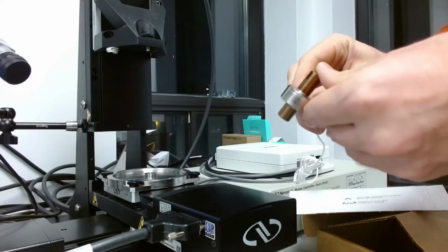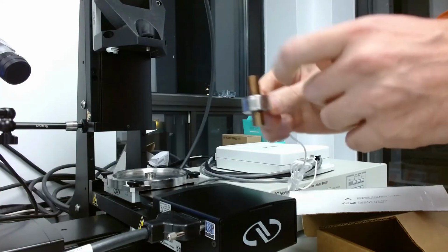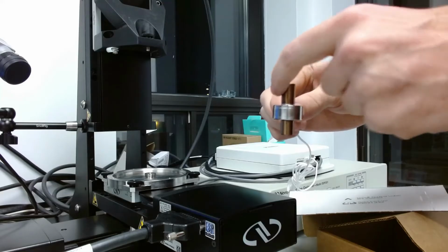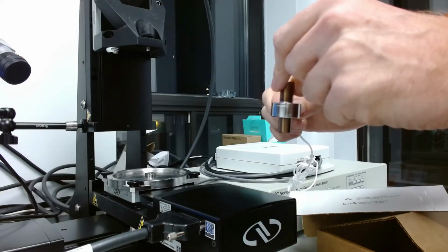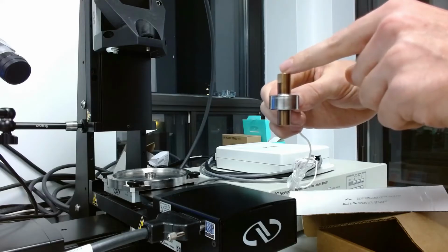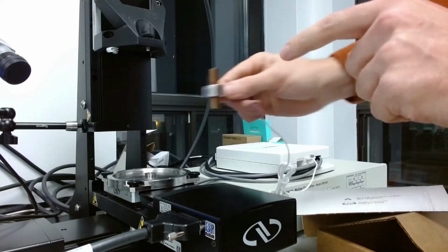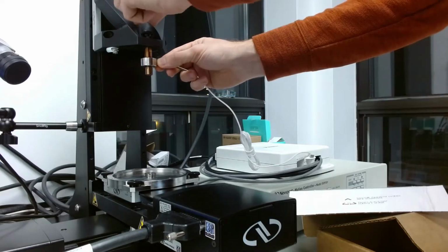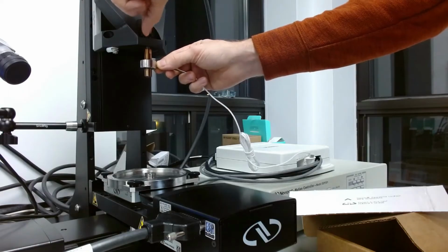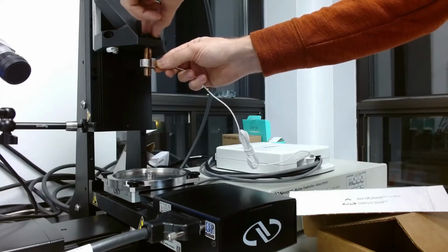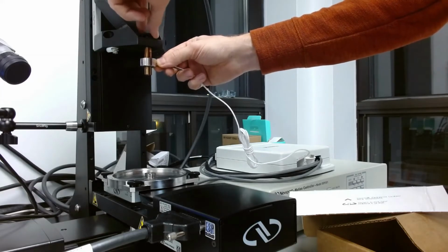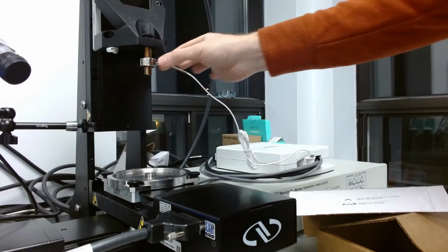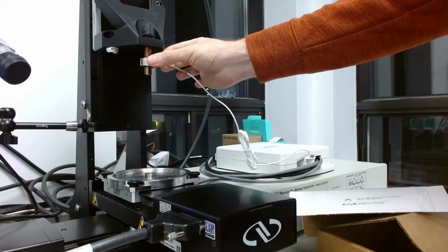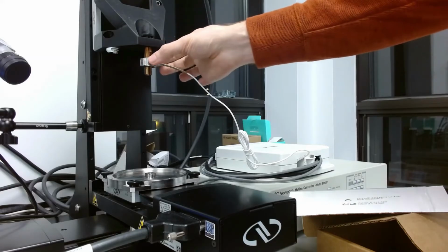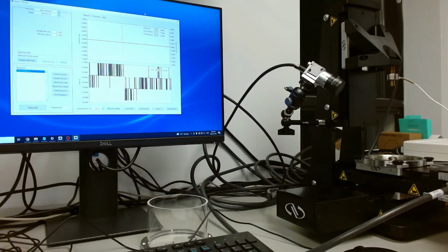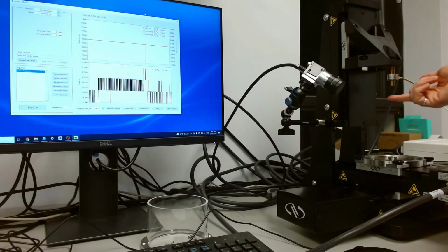Next, when we install this load cell onto the system, we're always going to install it from the side that's welded to the load cell body. What this means is the side with the notches will go against the machinery. What I'm doing here is taking the 1/4-28 thread thumb screw and installing the load cell until it doesn't move anymore. I'm just going to do a little check by touching only the body or the notched section to make sure that it's solid.